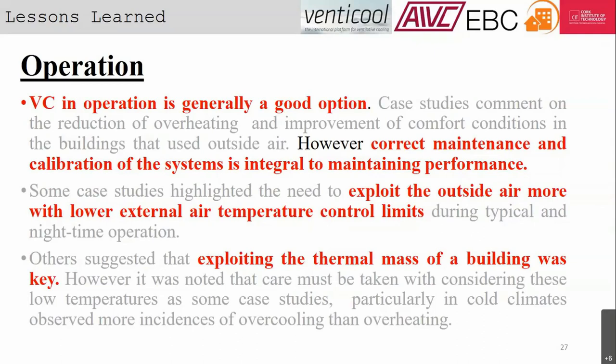In summary, VC is generally a good option. Correct maintenance and calibration is integral. We need to exploit outside air more with lower external air temperature control limits, and consider whether those limits change between daytime occupancy and nighttime operation, allowing variation in your low temperature control limit. Exploiting thermal mass was highlighted as absolutely key, but care must be taken — in cold climates, particularly during shoulder seasons when transitioning from winter to summer, overcooling can be a problem.